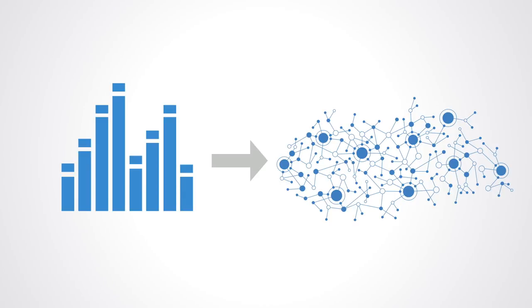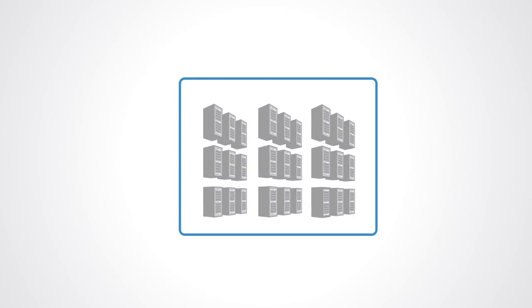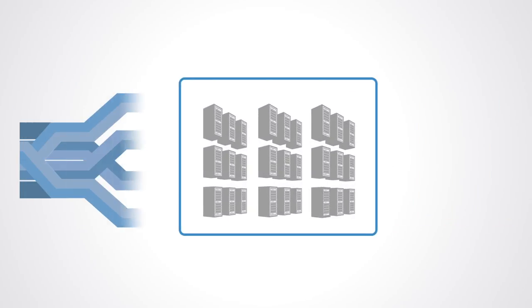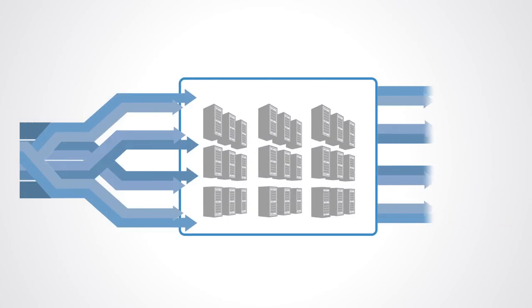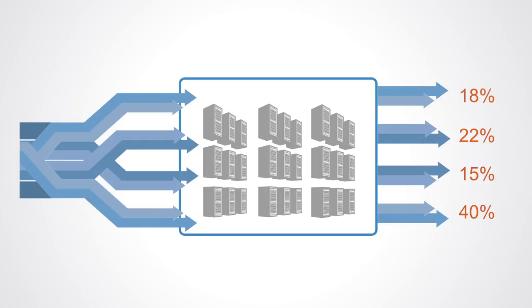They accomplished this by taking the historical data that had already been collected by thousands of sensors within the data center and using it to train a set of deep neural networks. The machine learning system analyzed the internal arrangement within the data center and tried different configurations to assess the efficiency of energy consumption. It stays iterating, adjusting the configuration, and trying to reduce the value and learning at each iteration. Ultimately, the algorithm managed to reduce the amount of energy used for cooling by up to 40%.